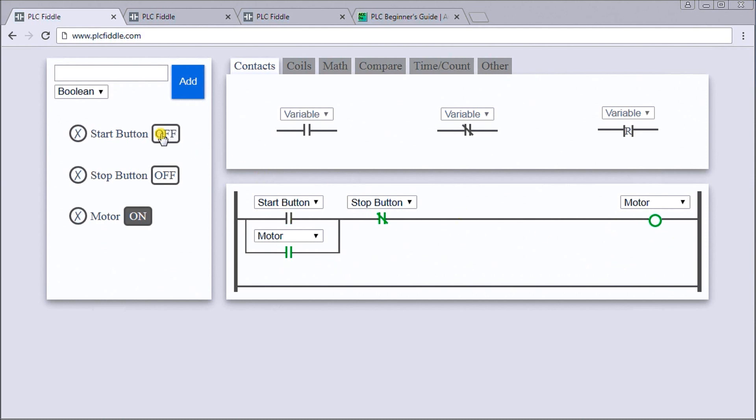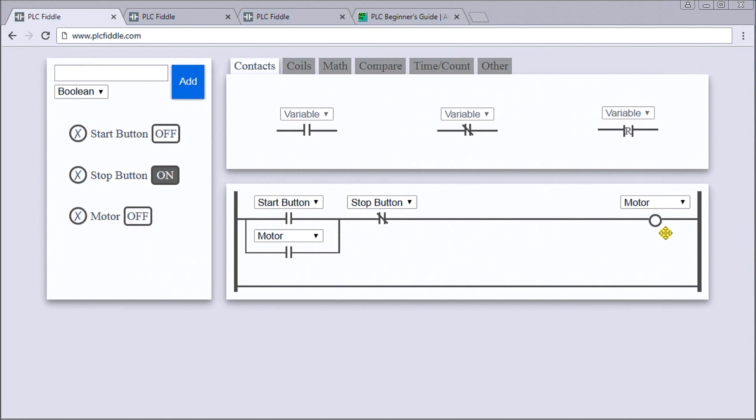We can turn off the start button and the motor stays on by our sealing contact that we have right here. We can then hit the stop button and the stop button bypasses or stops the flow from left to right, turns off the motor, and we go back to the very start again.